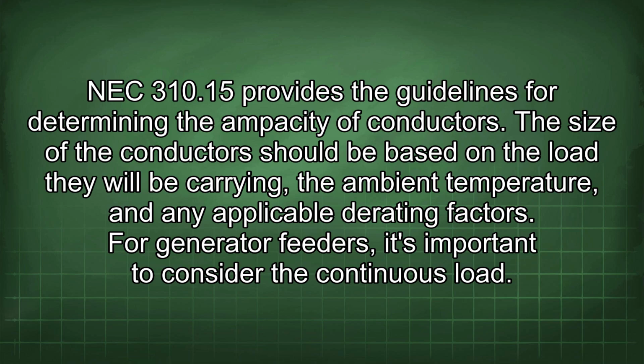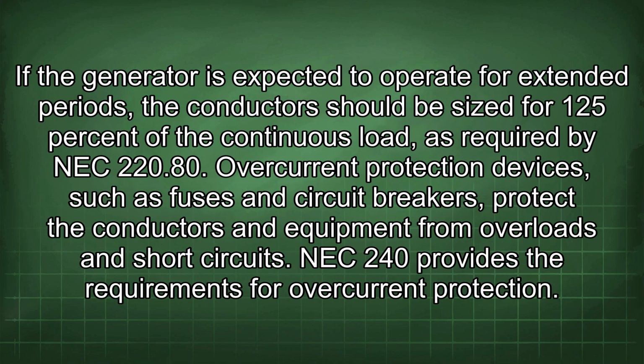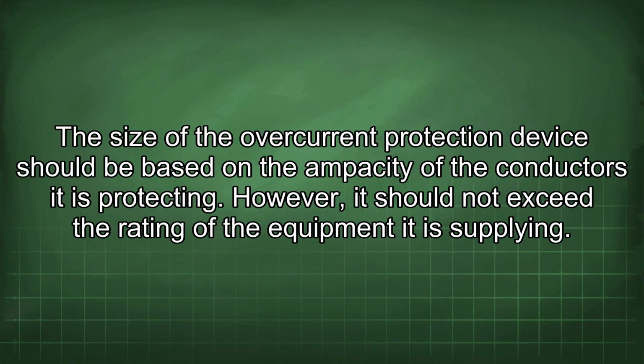For generator feeders, it's important to consider the continuous load. If the generator is expected to operate for extended periods, the conductors should be sized for 125% of the continuous load, as required by NEC 220.80. Overcurrent protection devices, such as fuses and circuit breakers, protect the conductors and equipment from overloads and short circuits. NEC 240 provides the requirements for overcurrent protection. The size of the overcurrent protection device should be based on the ampacity of the conductors it is protecting. However, it should not exceed the rating of the equipment it is supplying.